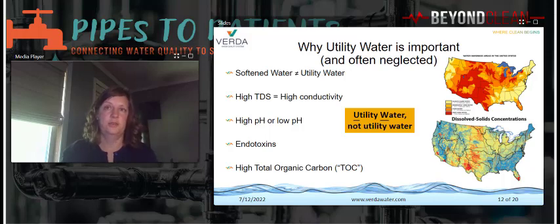The EPA regulations for drinking water are not the same as AAMI utility water specifications. So municipal drinking water may be in compliance, but still not meet utility water standards. Facilities management may be knowledgeable about drinking water requirements, but not realize these do not always meet AAMI regulations for water use in the SPD. If your facility is only softening the municipal water, that doesn't necessarily mean it's acceptable for utility water.